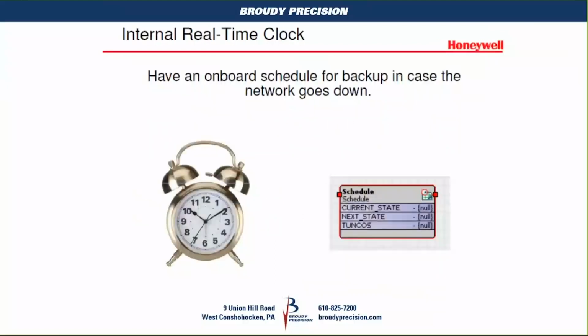Worth mentioning, back in 2007 when the Spyder first came out, it was one of the few twisted pair controllers on the market that had an onboard clock. That's only significant if you need to know the time and date. For example, on a boiler plant, I want to enable my boiler below 40 degrees outside air. I don't really care what time or date it is. All I care is that it's cold out.